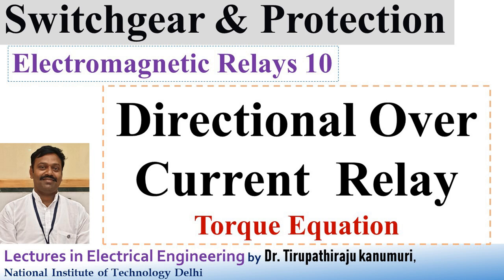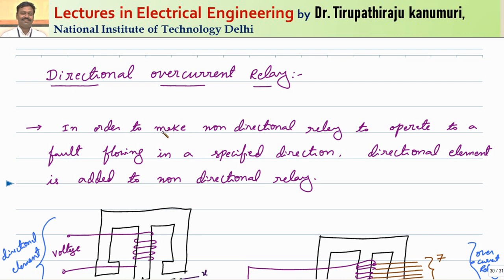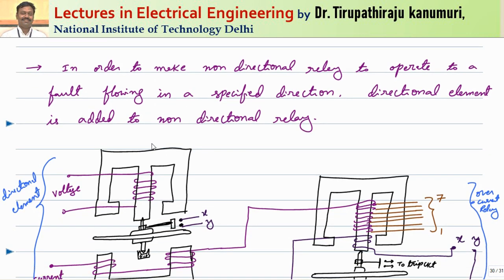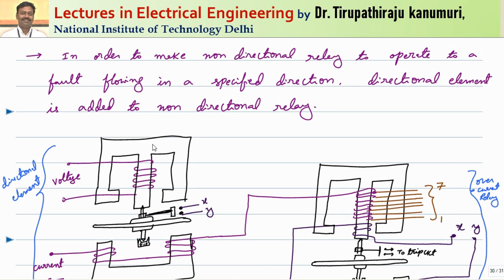Hi all, today we are going to discuss about directional overcurrent relays. We have already seen the non-directional overcurrent relay in our previous class. The disadvantage of the non-directional overcurrent relay is it will respond to overcurrent in both directions — it cannot sense the direction of the fault. There are some applications like feeder lines where two parallel lines are present, and in that case we need a directional relay.